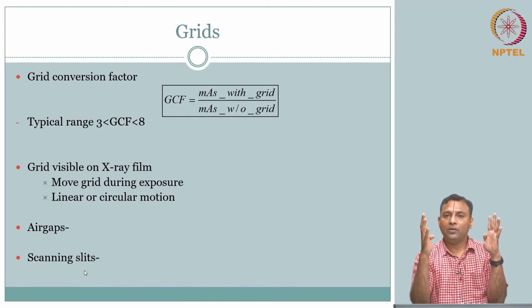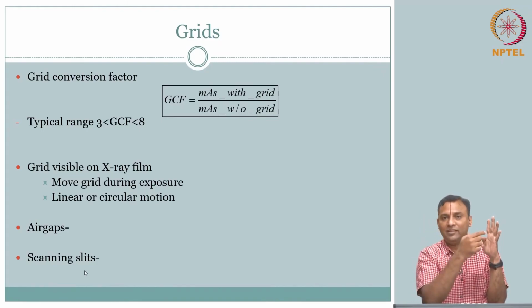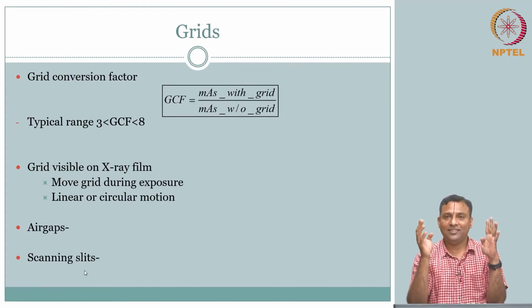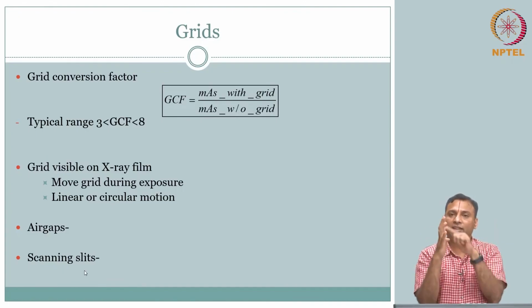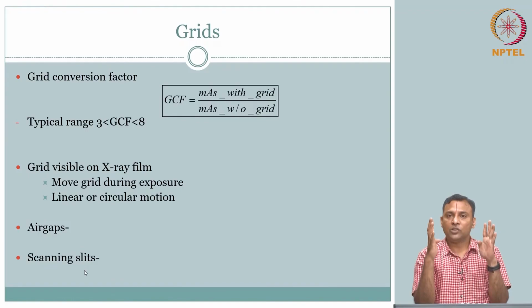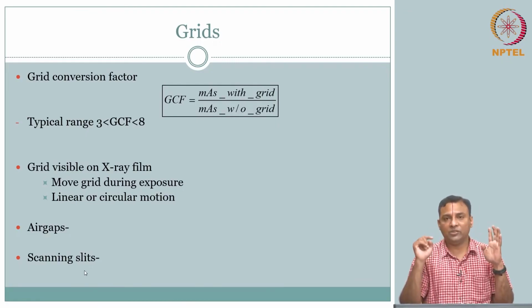So now what will happen? Oh, now we get the best of both, but the only problem is the signal is lost, you don't get signal. So you have to increase the exposure. And also in this sense, you are not scanning, you are not going through certain locations wherever the slit is not allowing in. So what we can do is have these two slits and move these slits, what we call scanning through the slits. This way you can reduce the scattering, you can increase the signal as well. So it's very effective in reducing the scatter.